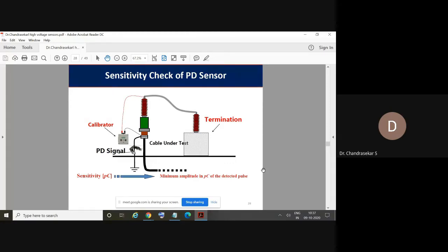You can easily visualize it in the computer. So like that, what is really a PD, and what is noise, and what is radio frequency interference or any other noise, we need to clarify those things, and that expertise should be developed by the test engineers. That's why the sensitivity check or calibration of the PD sensor matters, and understanding whether it is really a fault inside the transformer or cable, or some unwanted noise coming from outside. We need to distinguish those things.